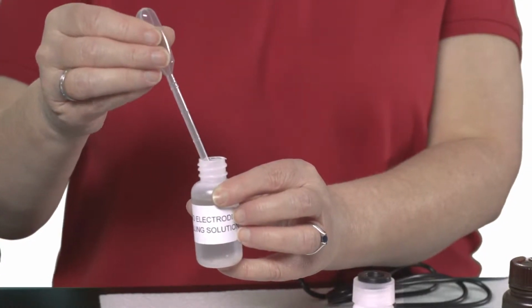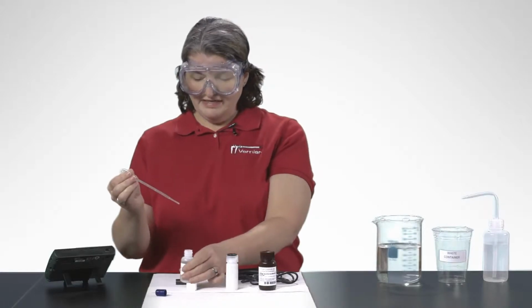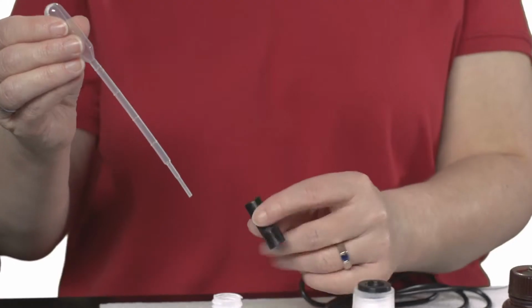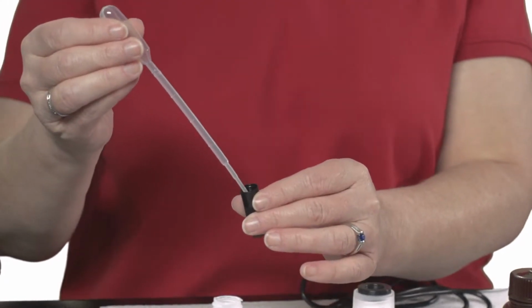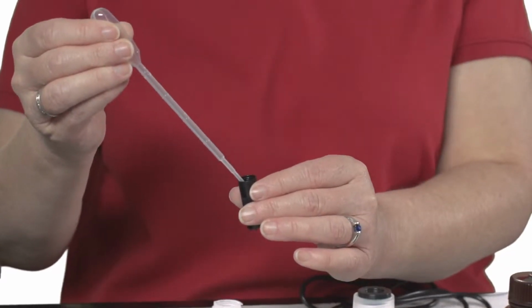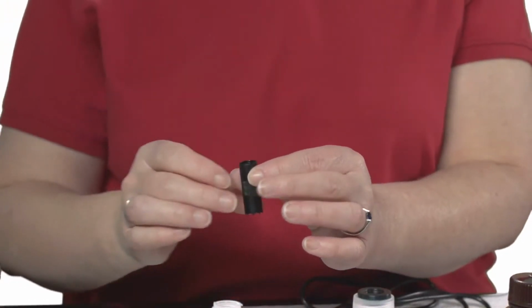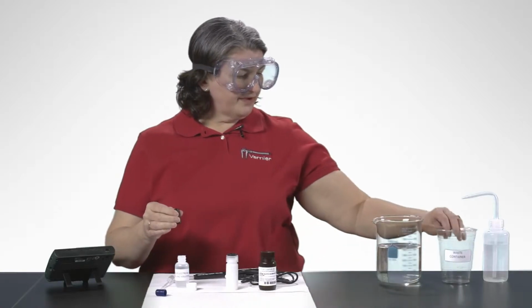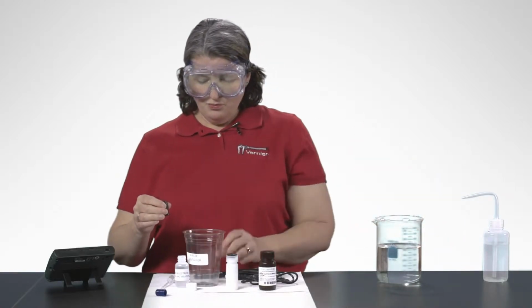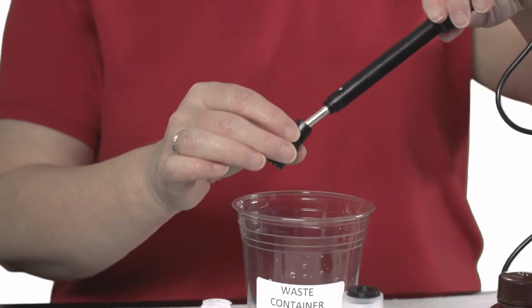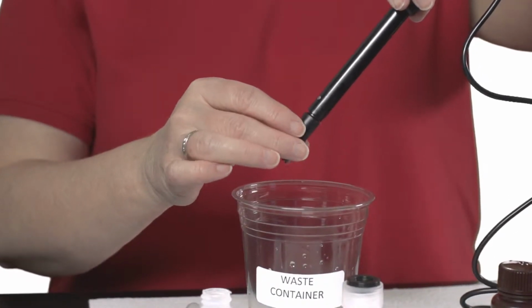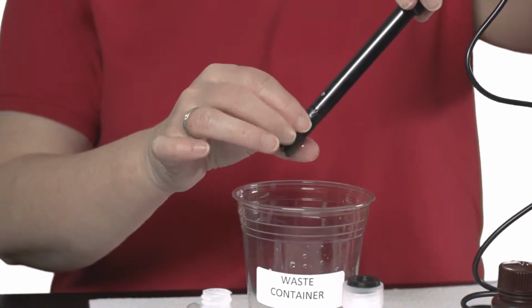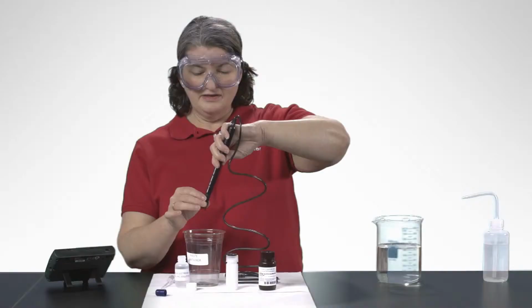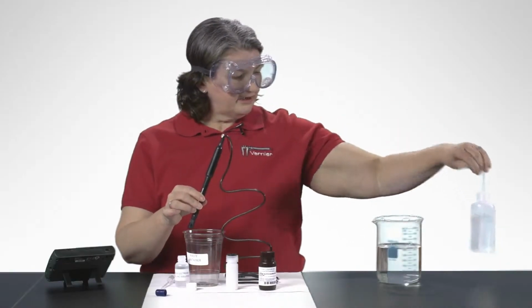And if you ever don't have this pipette available, you don't really need it, because all you're going to do is put in enough filling solution so that it goes to the bottom of the little threads inside the cap. We want it to be overflowing. So when you put the cap back on the probe, what we're looking for is a little bit of overflow. 1 or 2 drops is all you need, but a little bit. And there they go. Perfect. And I'll rinse that off.